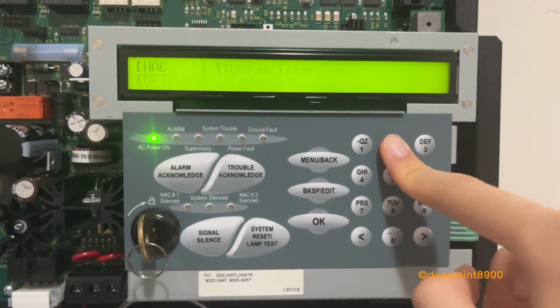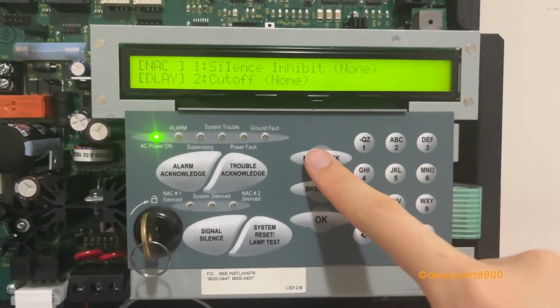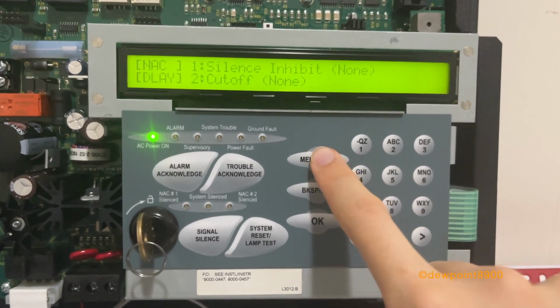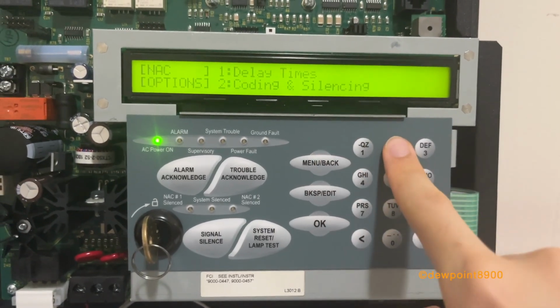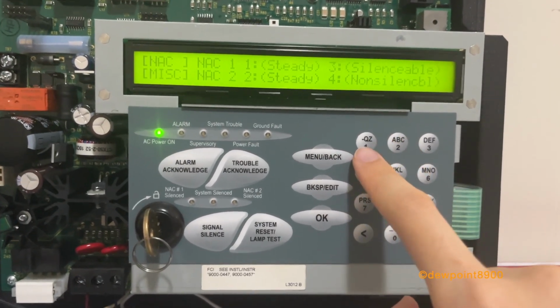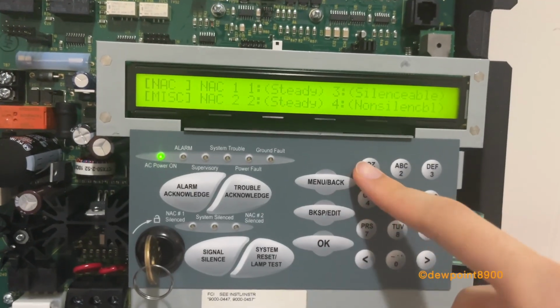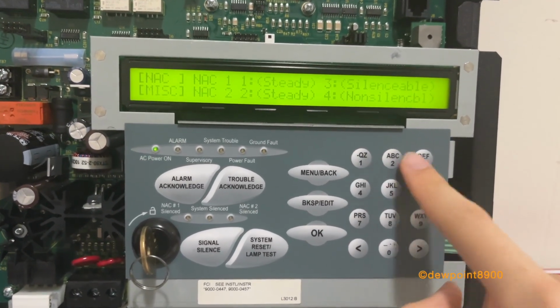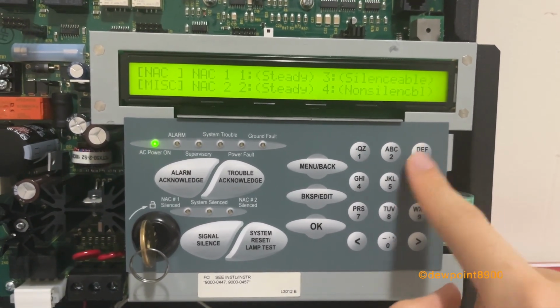Then you go to next. You can set the delay times, silence inhibit or cutoff. And there's also coding and silencing. So you can set either signal circuit to be either steady or coded, and then silenceable or non-silenceable.